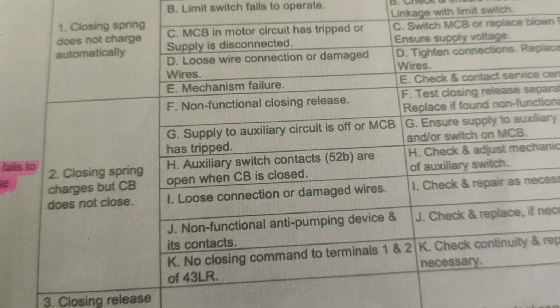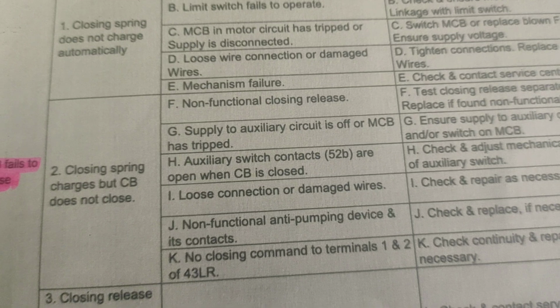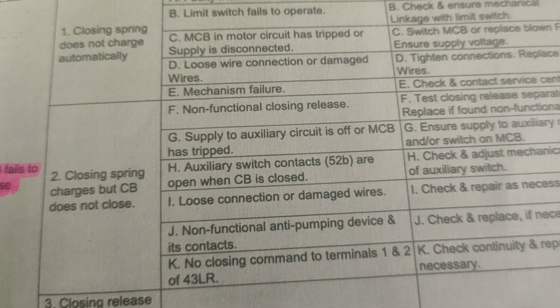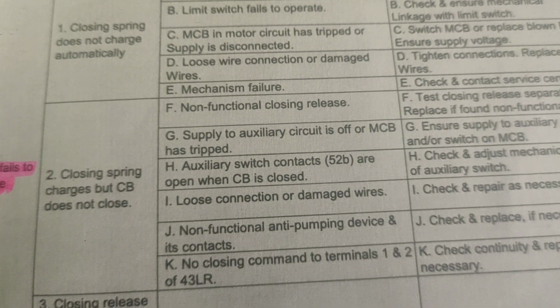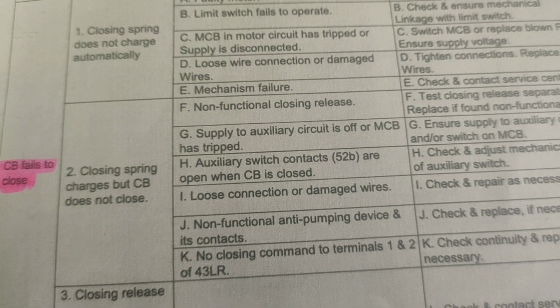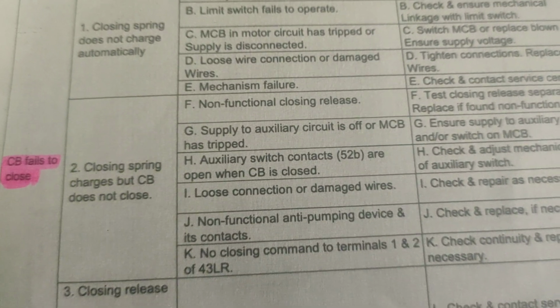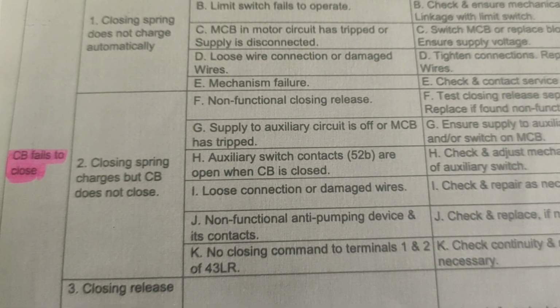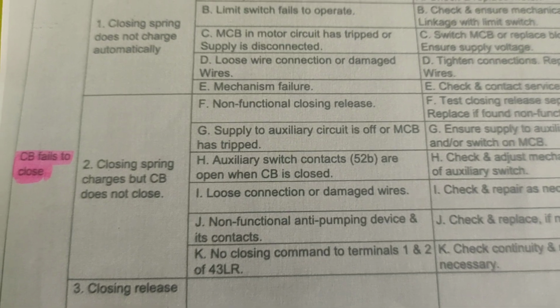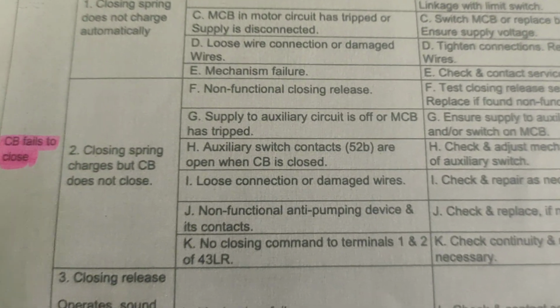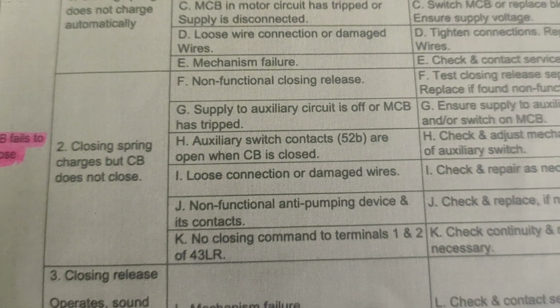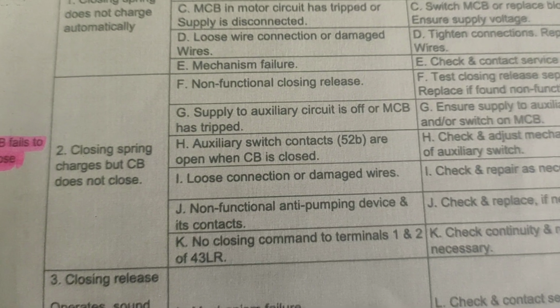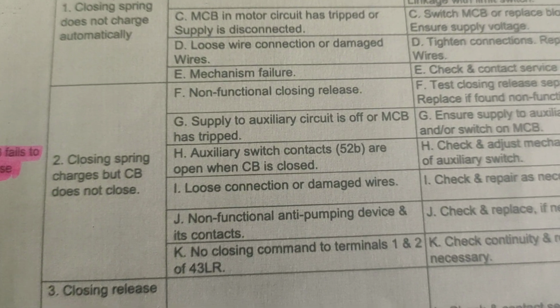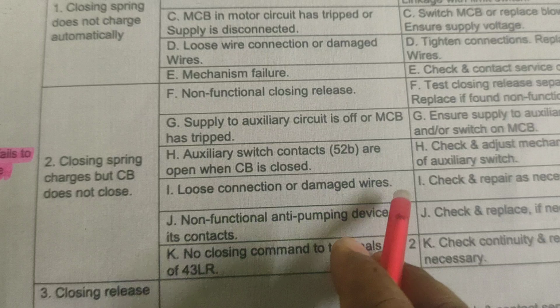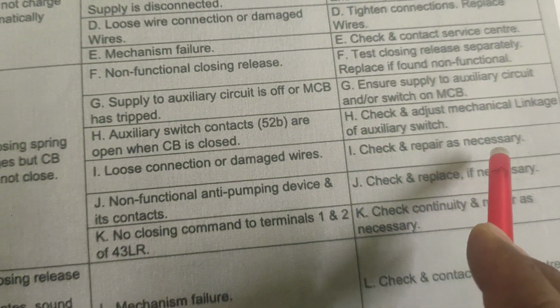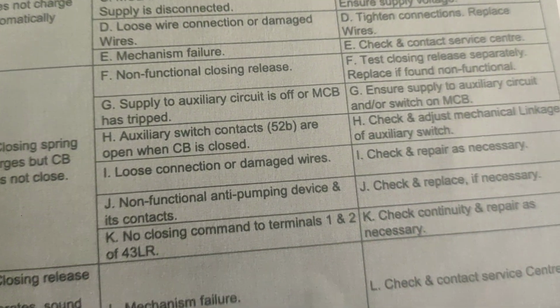So the DC, whether 220 volt DC, 110 volt DC or 30 volt DC, whatever DC is present in your substation or power plant, this DC will go to the closing coil, and the closing coil will generate the thrust and torque, and that torque will be utilized to bring the circuit breaker to the closed position. And for loose connections or damaged wire, check and repair as necessary.